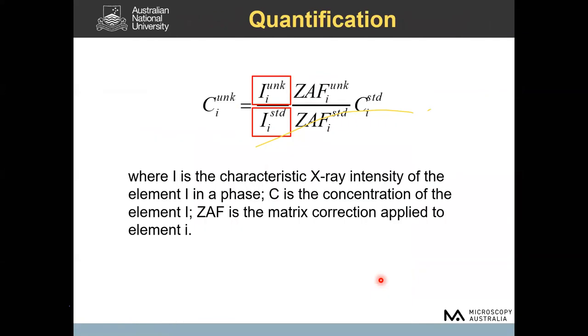By comparing the net intensity of the characteristic X-ray of elements in your unknown sample to the same X-ray in a standard reference material whose elemental concentration is known, and applying a matrix correction factor ZAF, you can obtain the concentration of the element of interest in your unknown sample. This procedure is exactly the same as how quantitative EDS works. For more details, I refer you to the video of yesterday's talk, which will be uploaded to the YouTube channel.